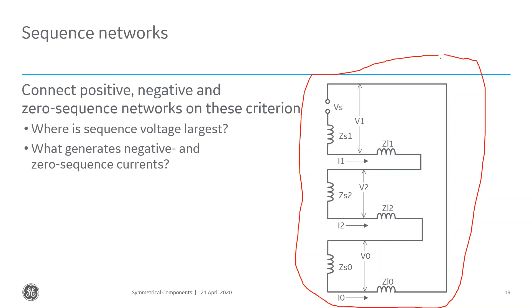These three sequence networks interact differently for different fault types. For a phase-to-ground fault, my metering location sits within those networks. The voltage is largest in the positive sequence network right across the voltage source. My fault location is where these networks connect. As I get closer to the fault electrically, my negative sequence voltage increases while my positive sequence voltage decreases. My zero sequence voltage also increases as I get closer to the fault.